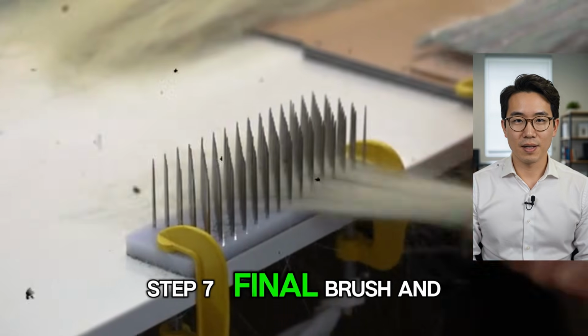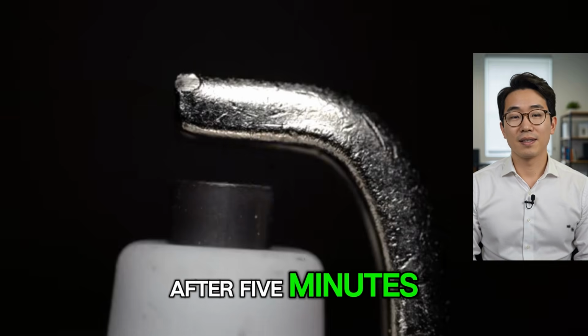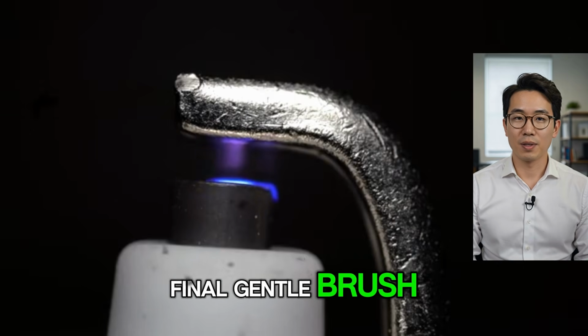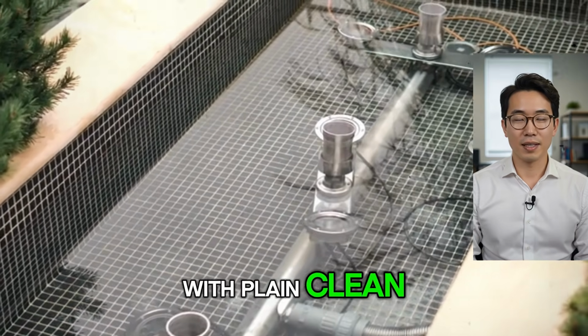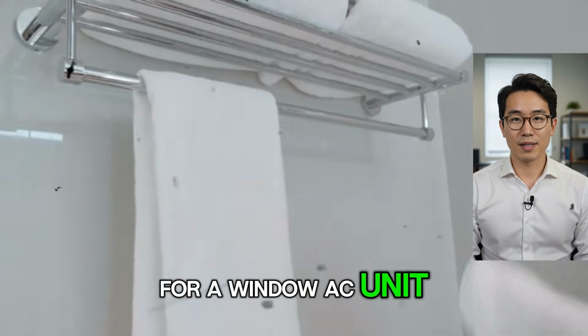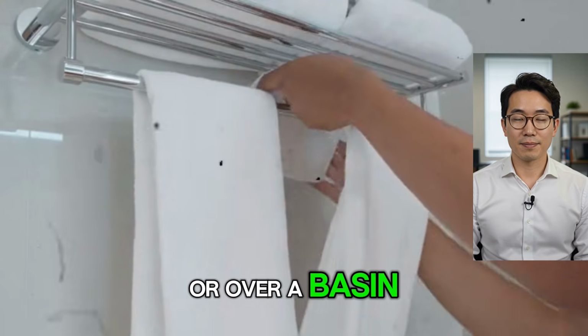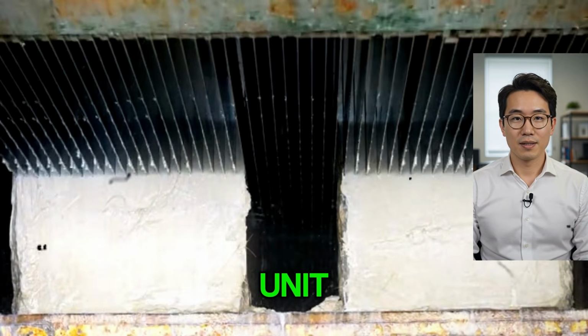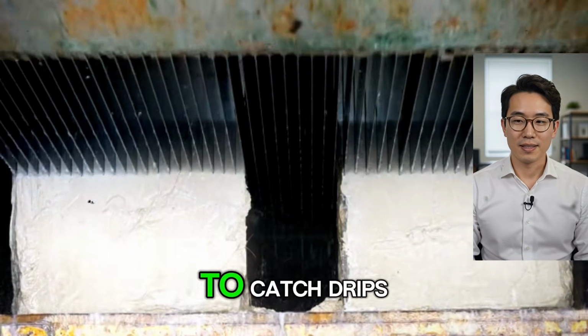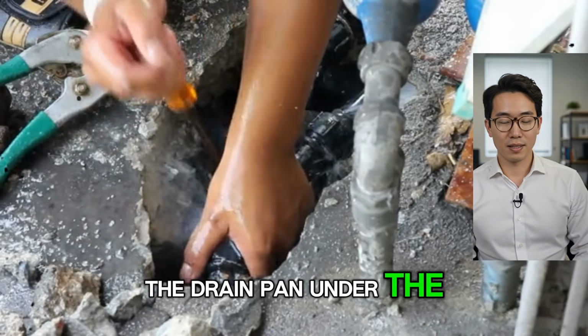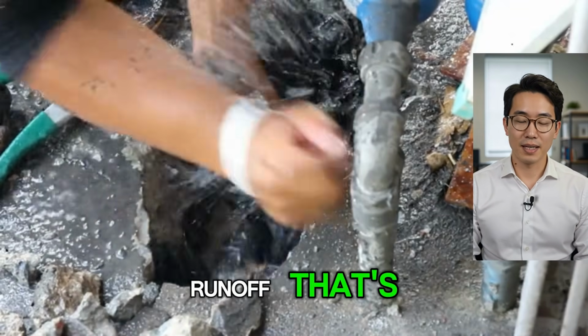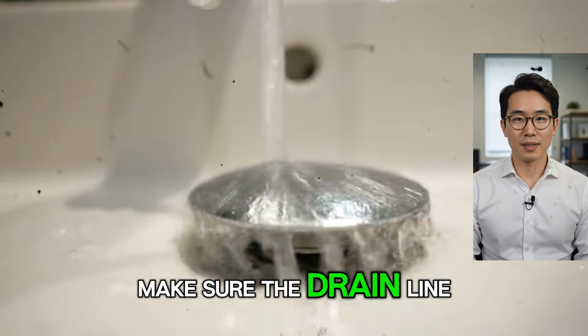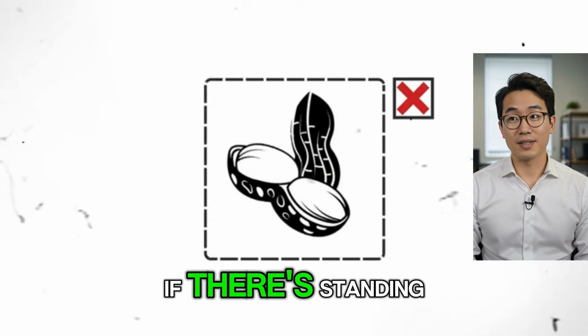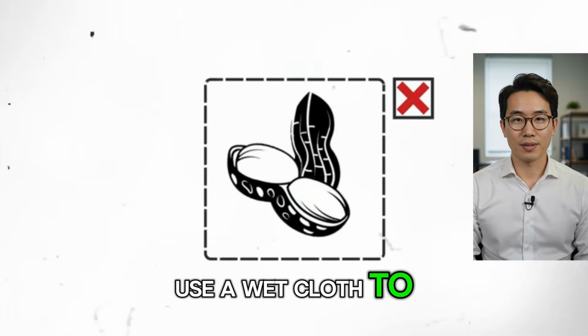Step 7, final brush and rinse. After 5 minutes, give the fins one final gentle brush. Then spray lightly with plain clean water to rinse. For a window AC unit, you can do this outside or over a basin. For a split system indoor unit, use minimal water and have a towel underneath to catch drips. The drain pan under the coil will handle most of the runoff. That's what it's designed for. Make sure the drain line is clear while you're in here. If there's standing water in the drain pan, use a wet cloth to remove it.